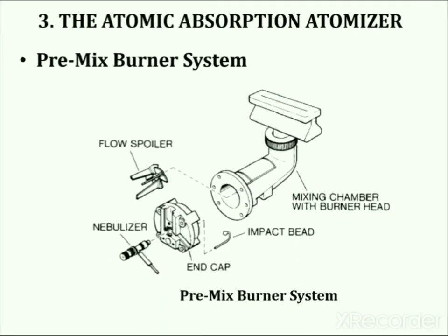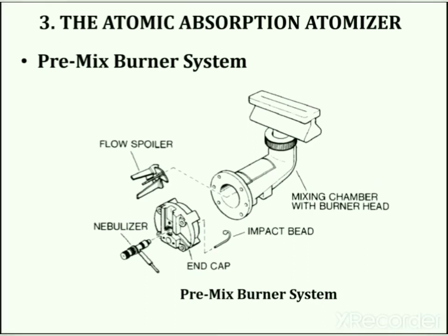The atomizer used in Atomic Absorption Spectroscopy is the premix burner system. The sample cell or atomizer must produce the ground state atoms necessary for atomic absorption to occur, involving the application of thermal energy to break the bonds holding atoms together as molecules. In the premix burner system, the sample solution is aspirated through a nebulizer and sprayed as a fine aerosol into a mixing chamber, where it is mixed with fuel and oxidant gases and carried to the burner head, where combustion and sample atomization occur.